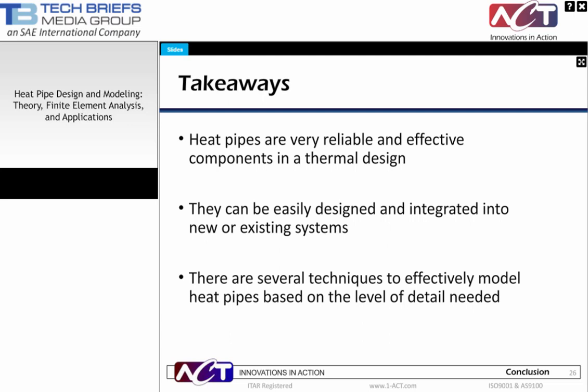In a high-K application, do the heat pipes need a finned heat sink on them to provide the condensation? The heat will be transferred wherever it's warm on the pipe. So as long as you have a delta T, you'll be evaporating somewhere on the pipe and condensing somewhere else. It doesn't necessarily need to be a finned heat sink, but you do need some place to reject the heat. Heat pipes are excellent at moving heat from one spot to another, but you still need the ultimate heat sink — it's just the physics of it.